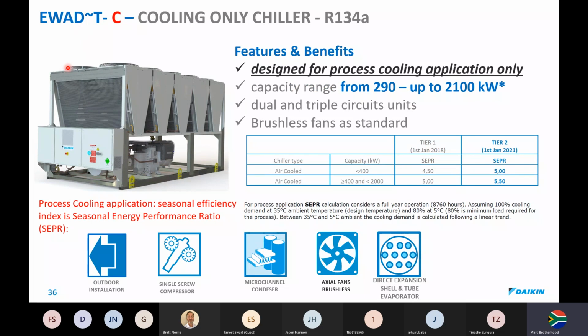We also do, and I've included this in the training, a chiller that is specific for process cooling only, also up to 2.1 megawatts. It's got a slightly different algorithm in the software. And importantly, for process cooling applications, you'll notice that most chillers work in EER, energy efficiency ratio, or SEER, seasonal energy efficiency ratio. But because we're cooling down a process where throughout the year the cooling load will be the same, be it a bakery, be it an injection molding plant where you're melting plastic, regardless of the outside temperature, you're cooling a set design load. So this is the kind of chiller that you would select.